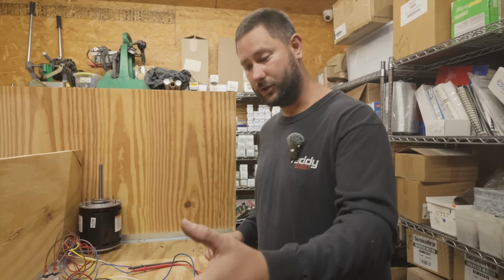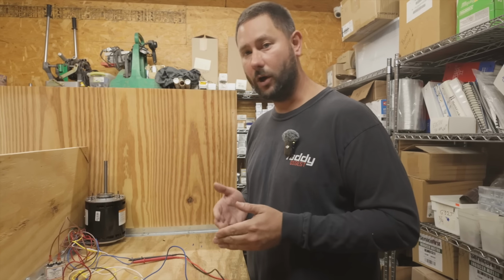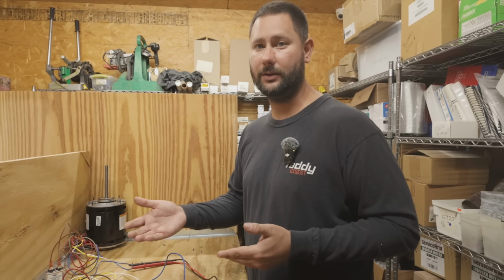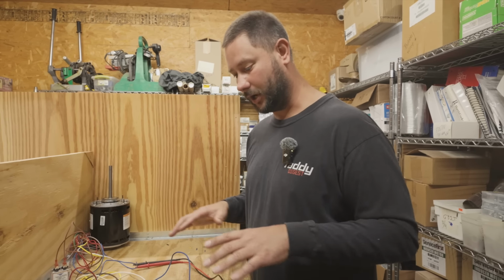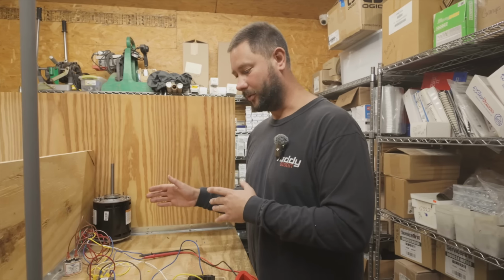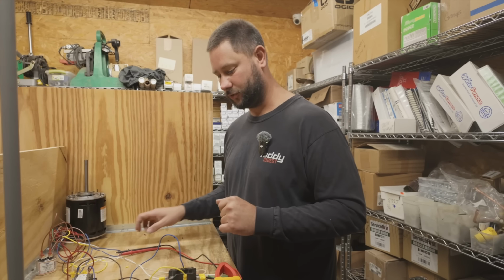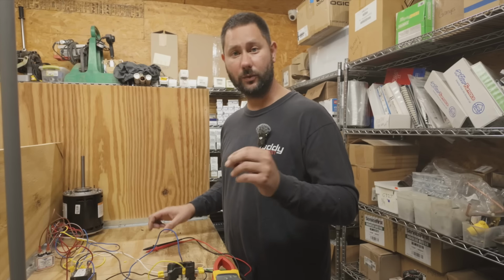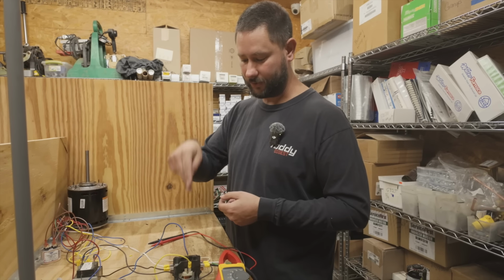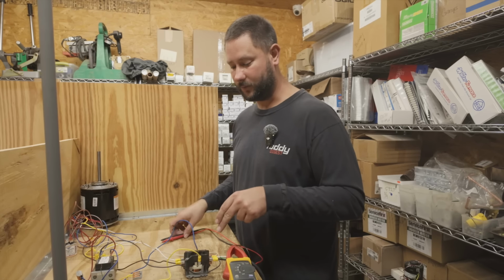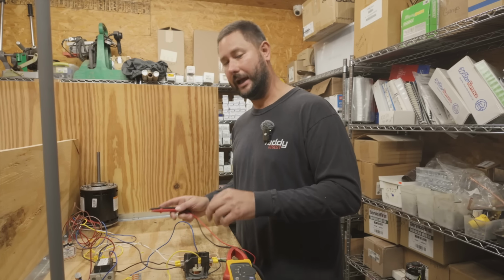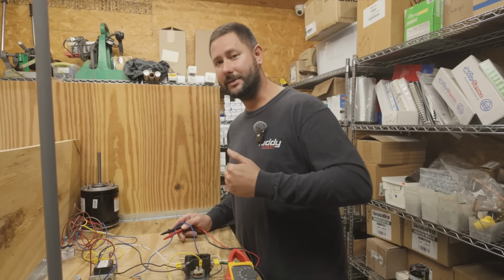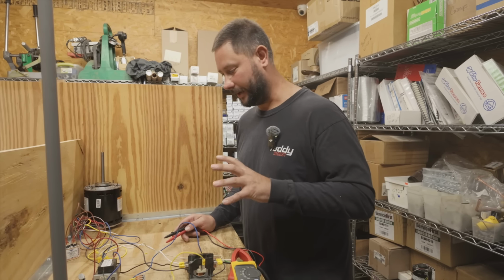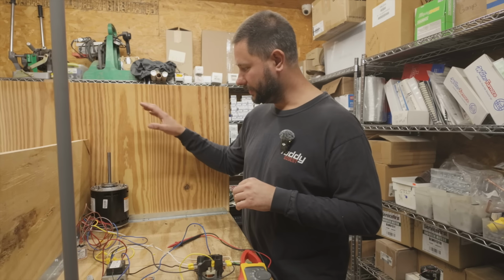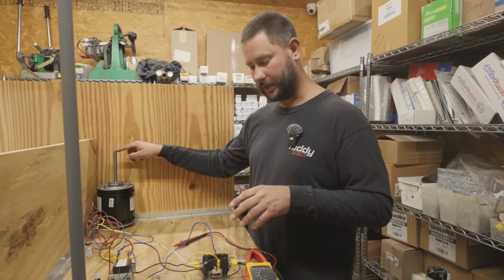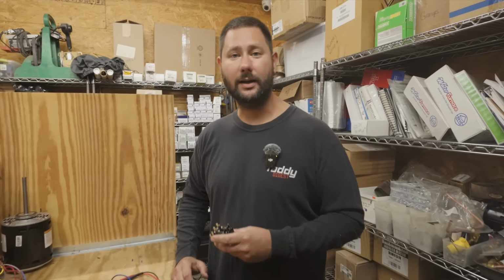All right, without the 120 volts coming into the contactor, there's no way we can have 120 volts on the other side of the contactor. So that is a basic overview so far. If you want to learn more about wiring on motors, remember, I've got that video down in the description. So now you know the 24 volts is what pulls in the contacts of the contactor, and it's what makes the contactor have voltage on not just the incoming side, but now the outgoing side. Hope that makes sense. We're able to run our fan motor with the contactor closing. Now you know how a contactor works.